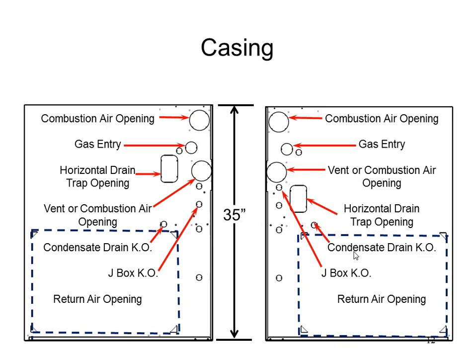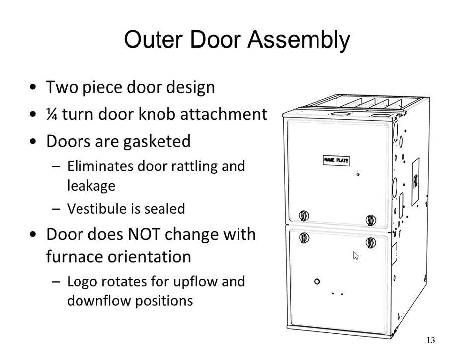All these furnaces can have services on all sides of them. So both the Bryant and the Carrier modulating furnace can have the gas come in the left side or the right side, electric left or right, return air left, right, or bottom, and combustion air left, right, or top, and the exhaust flue gases left, right, or top. And the condensate left or right. So everything can come on every side. It's very flexible on the installation side of the discussion.